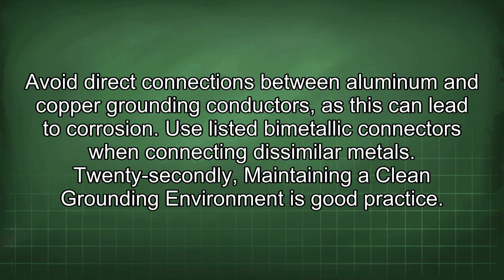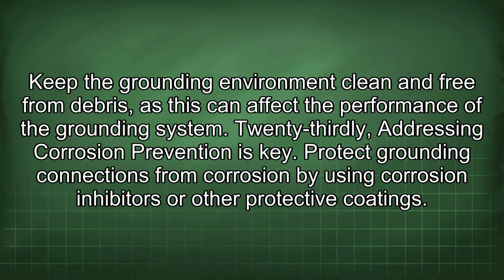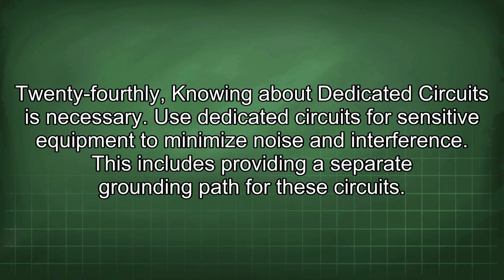Twenty-secondly, maintaining a clean grounding environment is good practice. Keep the grounding environment clean and free from debris, as this can affect the performance of the grounding system. Twenty-thirdly, addressing corrosion prevention is key. Protect grounding connections from corrosion by using corrosion inhibitors or other protective coatings. Twenty-fourthly, knowing about dedicated circuits is necessary. Use dedicated circuits for sensitive equipment to minimize noise and interference. This includes providing a separate grounding path for these circuits.